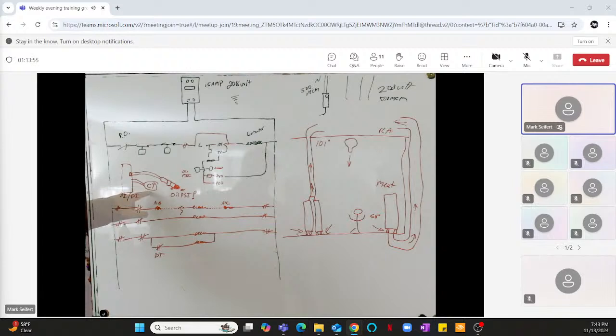But if the CT says, yeah, that compressor is running, and the oil pressure differential says, yeah, but I've got no oil pressure, it's going to wait a certain amount of time, whatever's in the program, and it's going to open the RO and lock it out. It's going to latch it. And that's when you're going to see it's got the oil pressure alarm, and you have to clear the alarm, and then it'll reset and it'll try again. So if it does have a CT, a run proof of any kind, it's going to... let's just say it doesn't have the CT. If the high pressure trips, it's going to trip on oil. It doesn't know if the compressor is running or not.